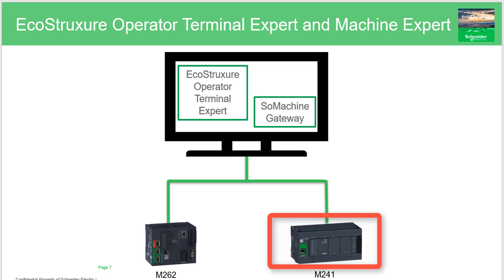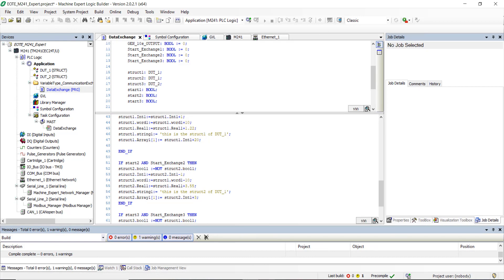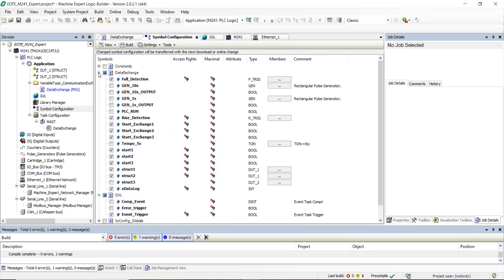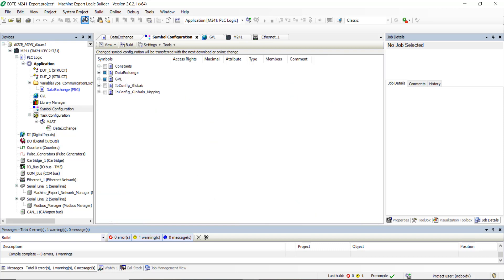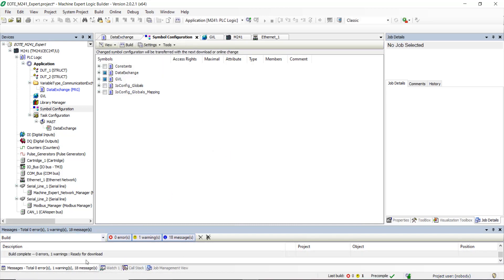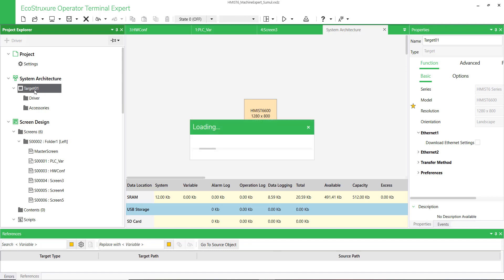In this first example we are going to use the M241 PLC. Here is the EcoStruxure Machine Expert application. In the symbol configuration, we have configured all the variables we want to use in the HMI application. To generate the XML file including PLC variables, click on Build then Generate Code. The XML file can be found where the EcoStruxure Machine Expert application is saved.